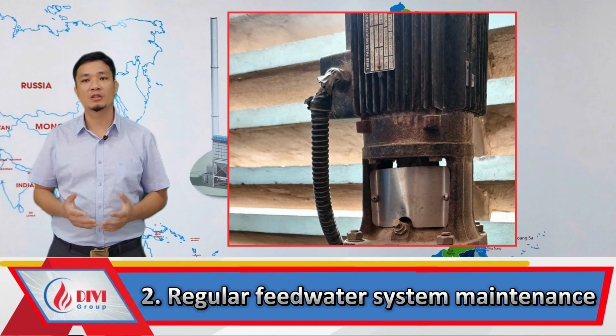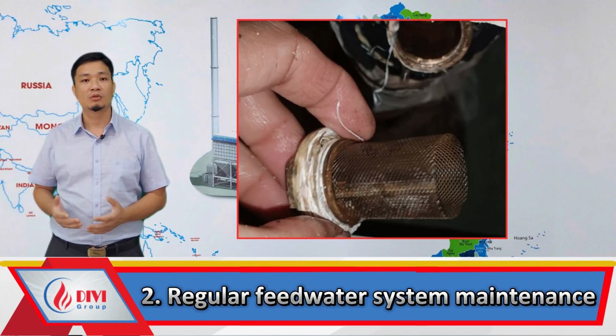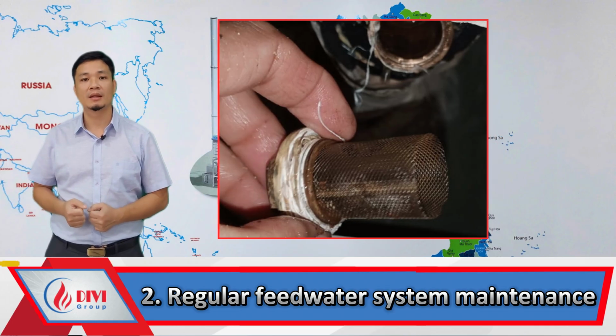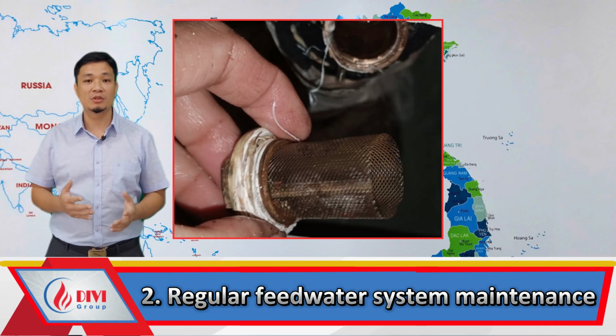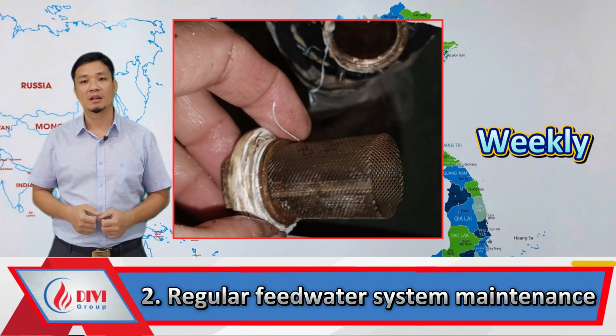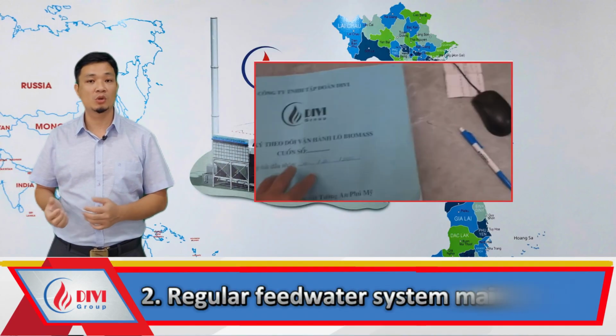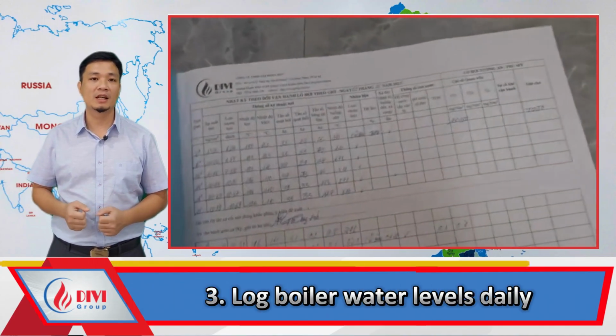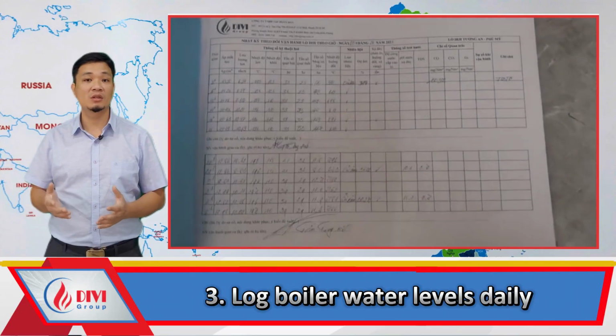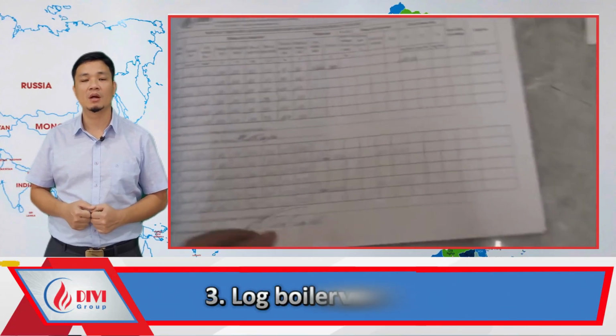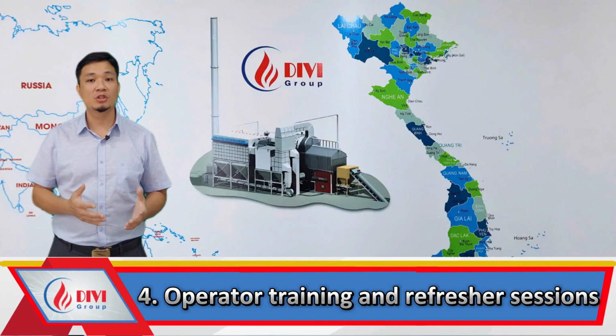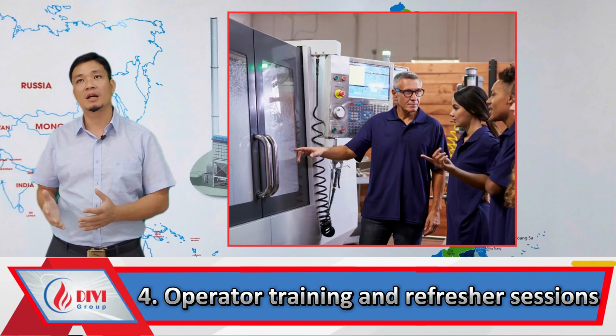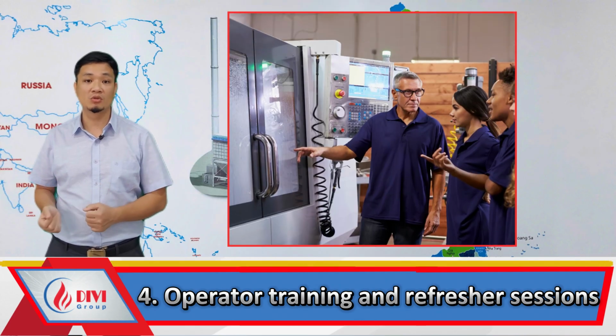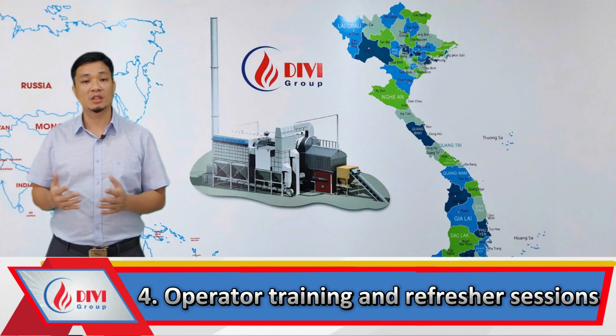Regular feed water system maintenance: clean filters, strainers, valves, and descaling treatment for pumps and economizers, ideally weekly. Log boiler water levels daily. Maintain operation logs to identify irregular patterns early. Operator training and refresher sessions. Train all boiler attendants in emergency shutdown, troubleshooting, and SOP adherence.